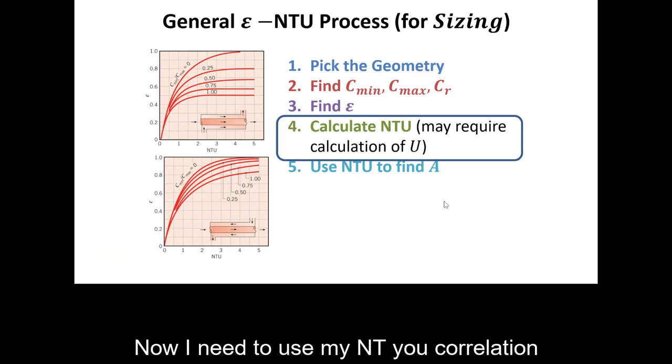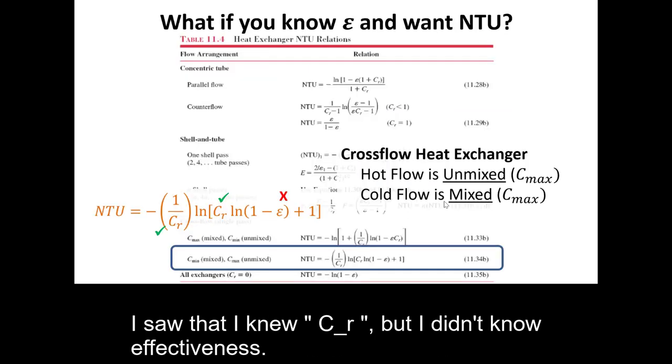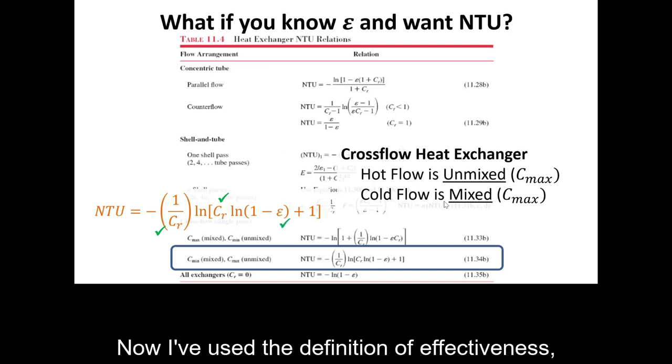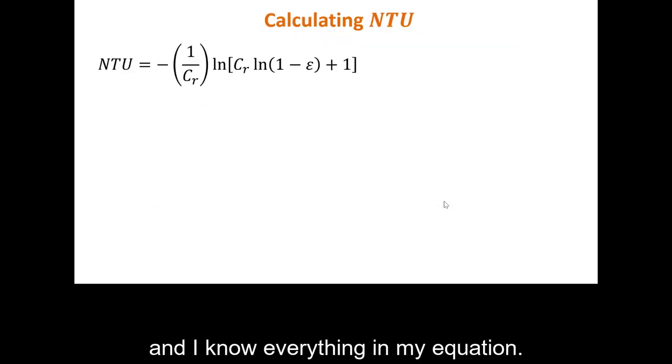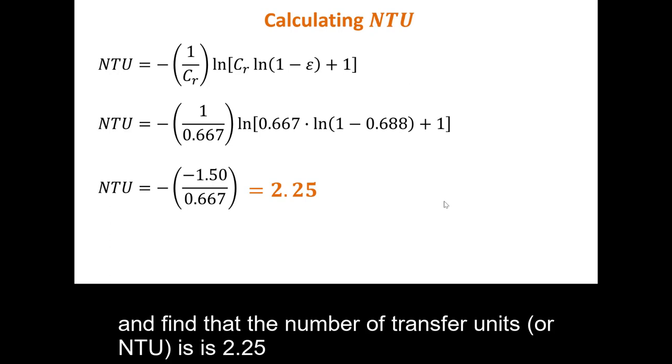Now, I need to use my NTU correlation to find NTU. The last time I looked at this equation, I saw that I knew big C sub R, but I didn't know effectiveness. But now, I've used the definition of effectiveness and I know everything in my equation. I can sub some numbers into my calculator, simplify it a little bit, and find that the number of transfer units or NTU is 2.25.